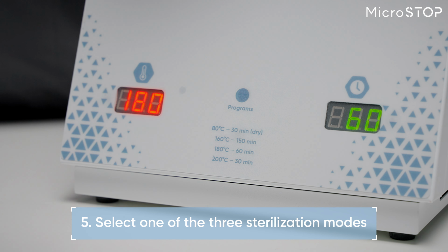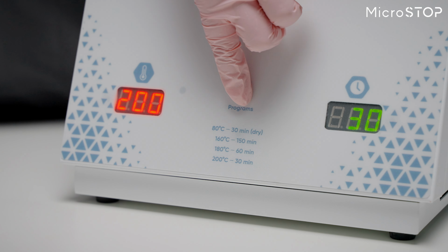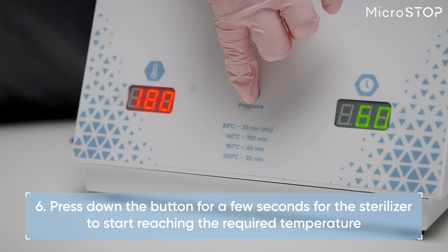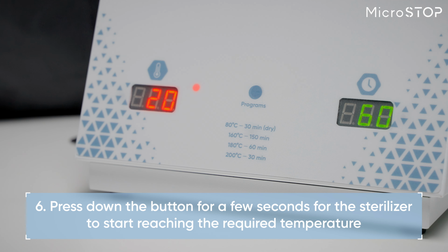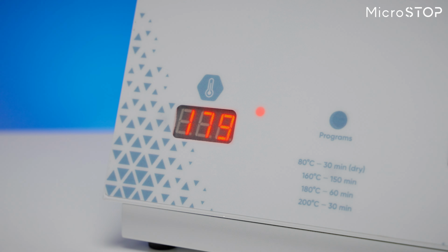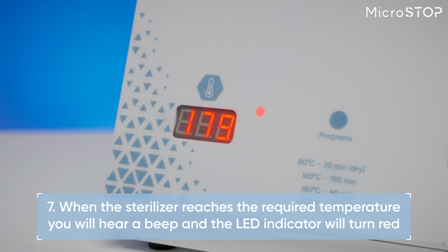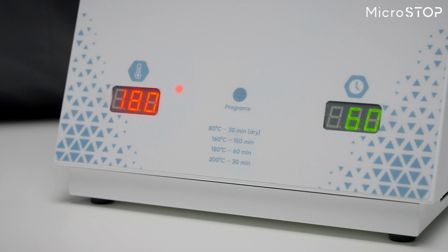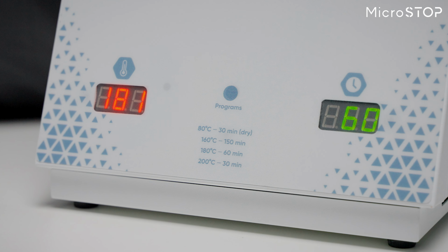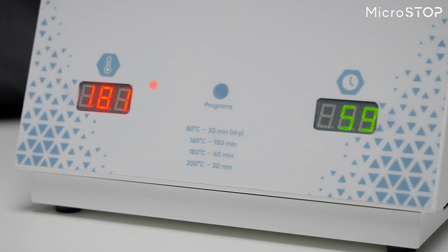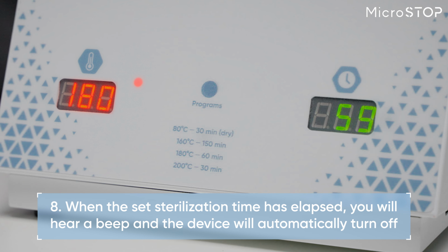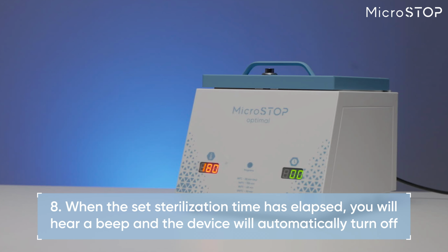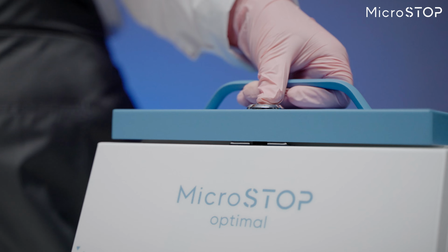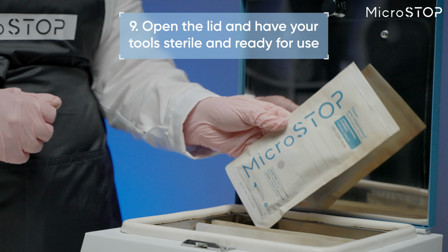Select one of the 3 sterilization modes using the button on the front panel of the case. Press down the button for a few seconds for the sterilizer to start reaching the required temperature. When the sterilizer reaches the required temperature, you'll hear a beep and the LED indicator will turn red. If you see a countdown on the digital display, it means that the sterilization process is in progress. When the set sterilization time has elapsed, you'll hear a beep and the device will automatically turn off. Open the lid and have your tools sterile and ready for use.